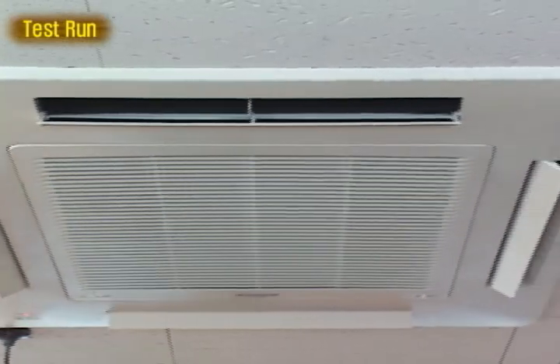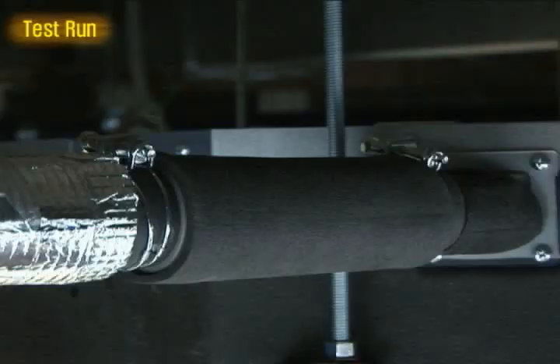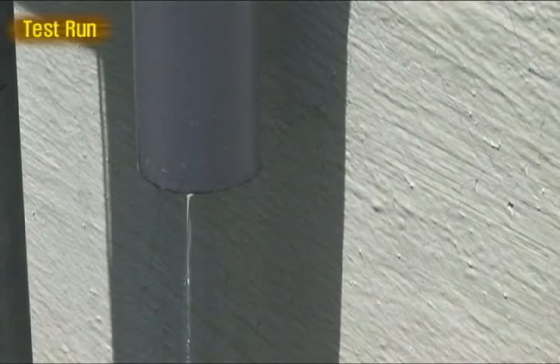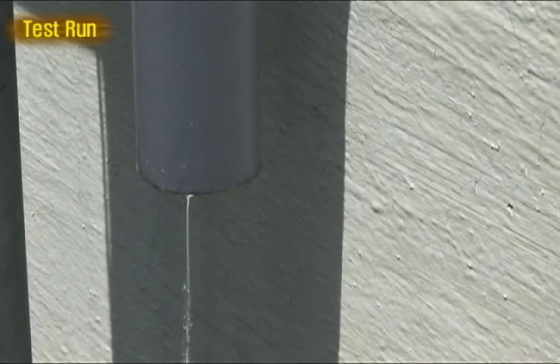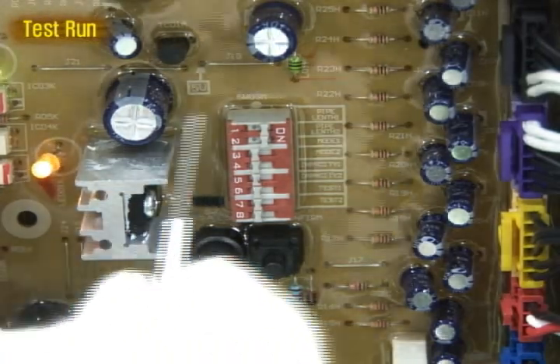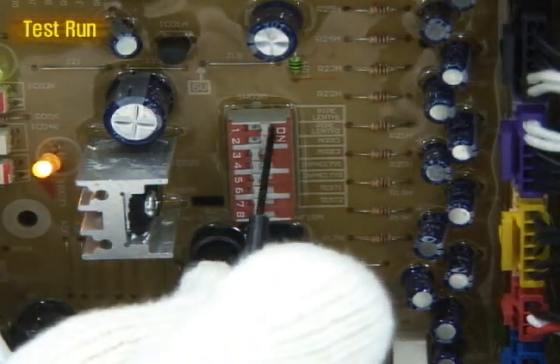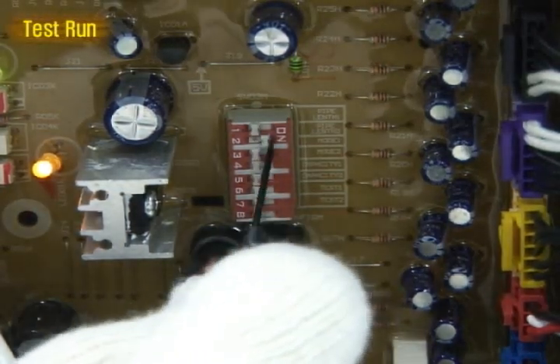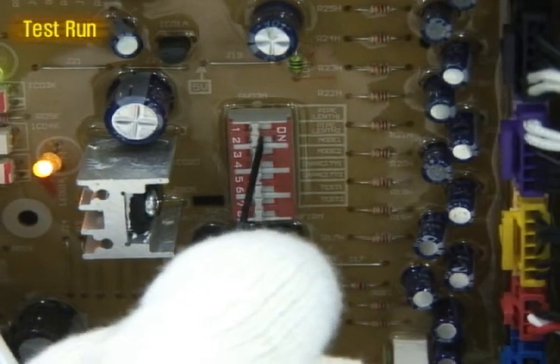During the test run, check the indoor unit indicator, abnormal noise, and other running status. Check the drainage line and review the flows. After the test run, set the dip switch of 1 and 2 to off, then reset the power.